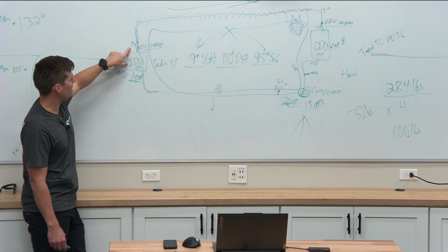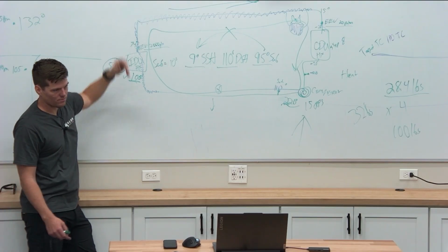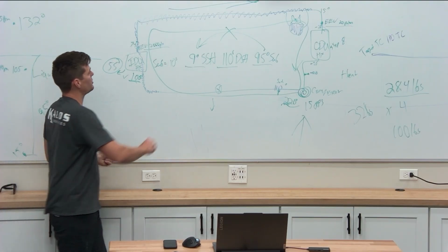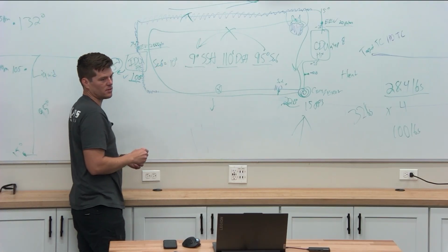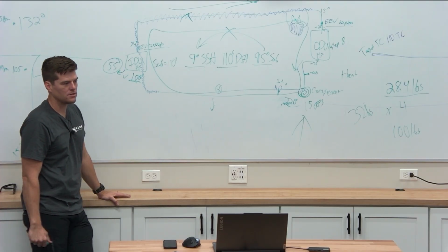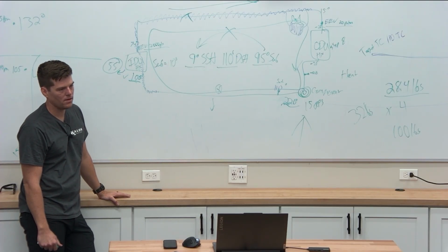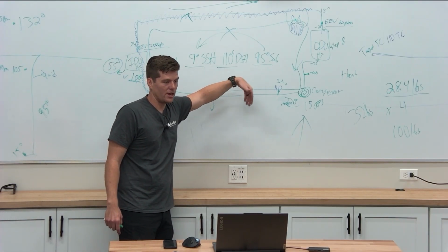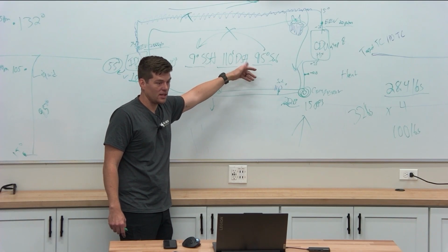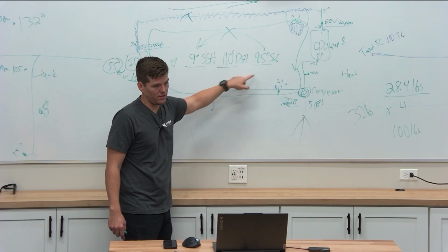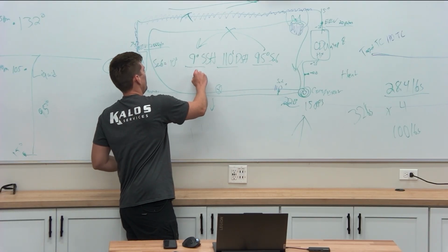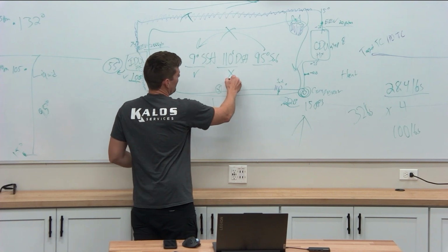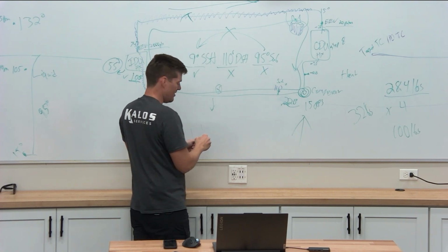Now, if I just had this and that, I would assume, right, the restriction is somewhere in the liquid line. Someone kinked it, someone broke it, someone did something, right? But I came to that conclusion because I did these 3 things, and then I turned around and I said, okay, let me go to this one because I really don't like that, right? This is good, check. This is bad, this is bad.